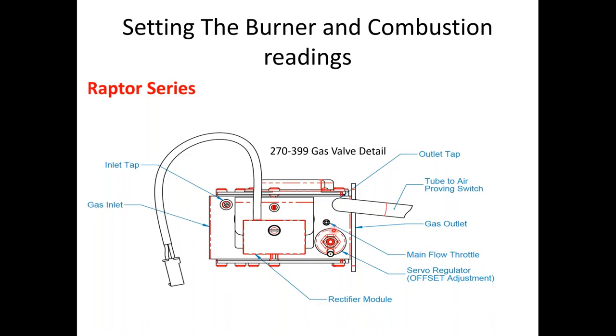Same thing is going to be with this. This is not as sensitive as the instructions make it out to be. Half turn to a full turn. Wait about 25-30 seconds for the analyzer to adjust, see where it's falling out, and then move it into place. In some rare occasions when we're setting these up, when we can't get high fire to fall into place, we get high fire as close as possible, drop down into low fire, dial in the low fire, and then go back up into high fire, and you'll notice that now we're able to get the ranges out of it. It's just changing the offset regulator's set points.